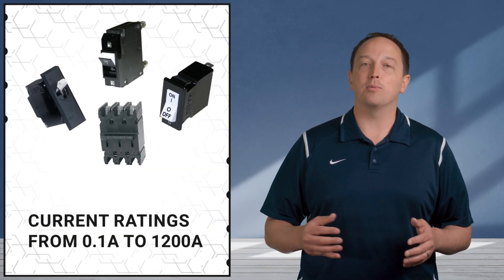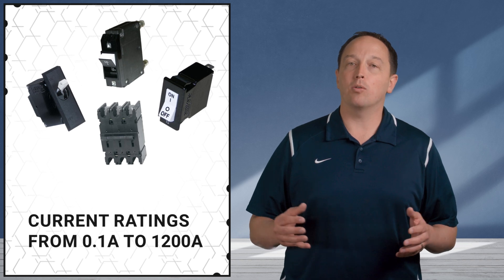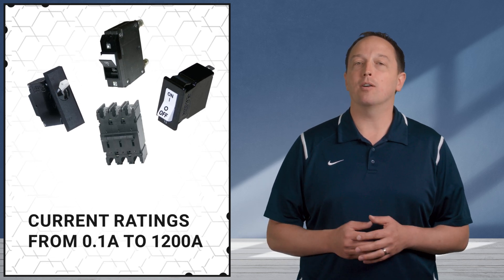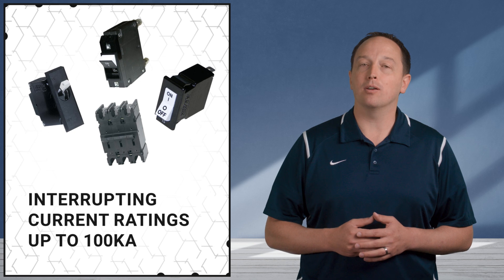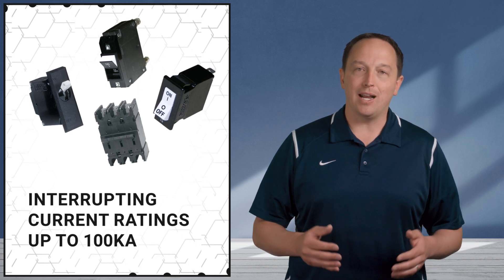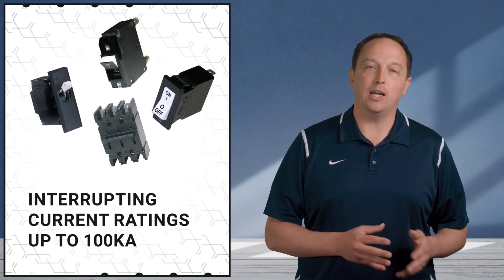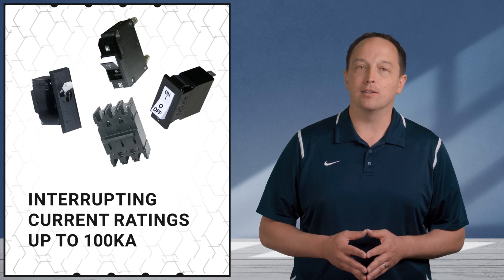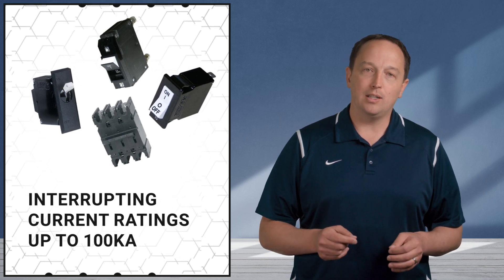These range from compact panel mount configurations to F-frame styles for up to six poles, with current ratings from one-tenth of an amp to 1200 amps, and interrupting current ratings up to 100,000 amps. They provide a consistent trip point over temperatures from negative 40 to positive 85 degrees Celsius and can be fine-tuned to one-tenth of an amp.